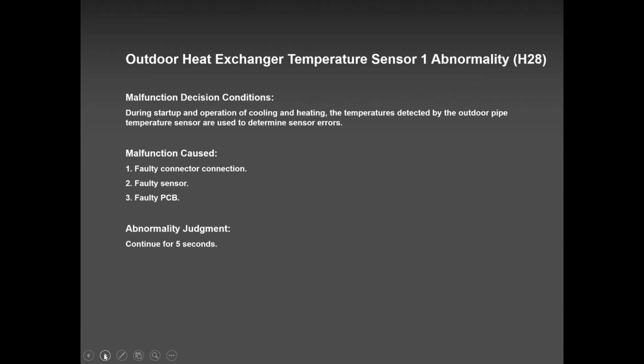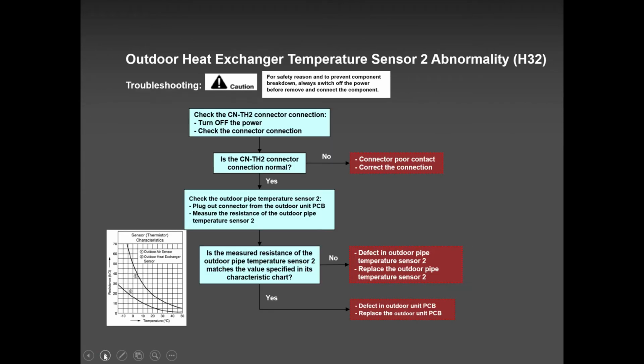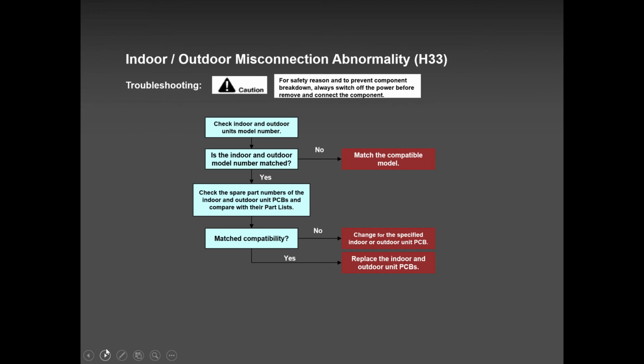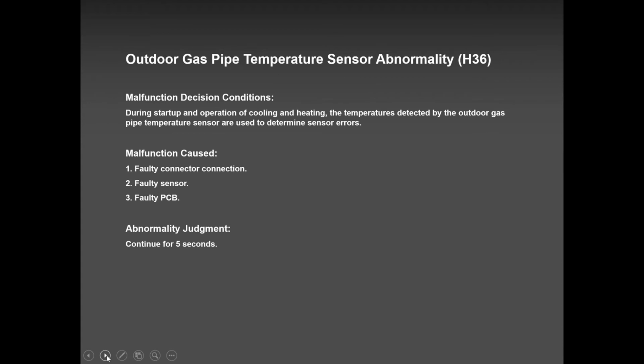Outdoor heat exchanger temperature sensor, again very rare, but it can happen. Okay. H32, outdoor heat exchanger temperature sensor. H33 is low voltage, indoor-outdoor miscommunication abnormality. Okay, supply voltage was low. In my opinion, H33 happened when I gave a 208/230 unit 115 volts. That's where it happened, the H33. H36 never happened, but you never know. It can happen to you, and that's the problem.